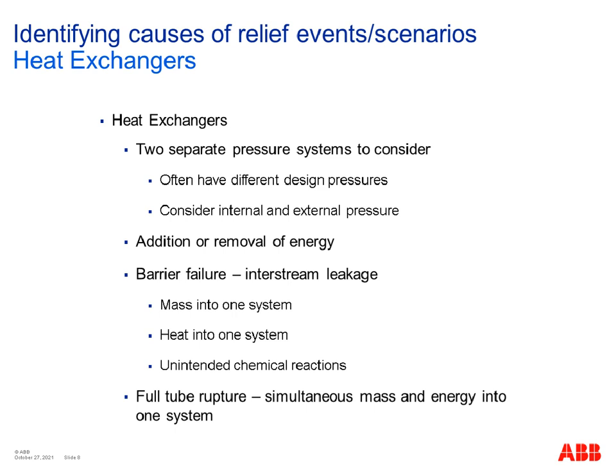The fundamental thing to remember about heat exchangers is that there are two separate systems involved. You have a high pressure side and a low pressure side, and they're separated by a metal interface. When considering pressure relief requirements, you need to consider each side separately, and consider the internal and external pressures for each of those sides separately. Also consider what happens in the event that the interface between the streams fails, in the event of a barrier failure, so the interstream leakage scenario.